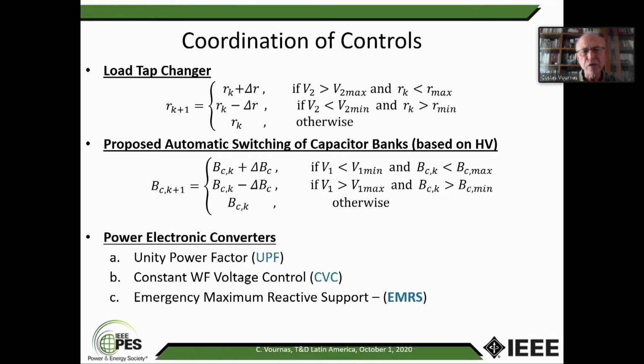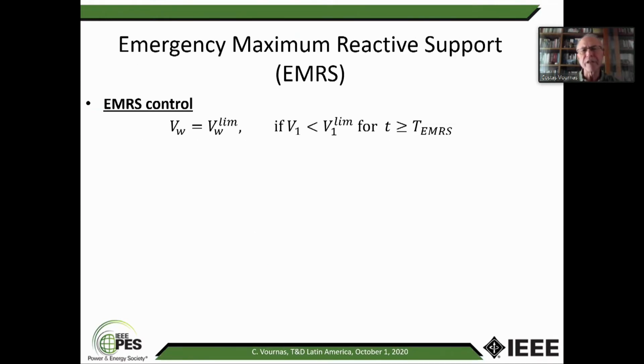The second case is when you have constant voltage control on the wind farm end of the feeder. And this is a case which can happen because the wind farm sometimes wants to maintain its voltage within limits. And the third case that I'm showing here is the emergency reactive support, which I'll explain in a minute. So for the emergency reactive support, we have the wind farm converter operating at constant voltage equal to nominal, 1 per unit voltage. But if the voltage on the primary falls below a limit, and as I said, in the case of the capacitors, if the transmission voltage is below 95%, you can switch on a capacitor. But if the voltage falls even more, let's say to 90%, then you need emergency support. And the emergency support is given by the wind farm.